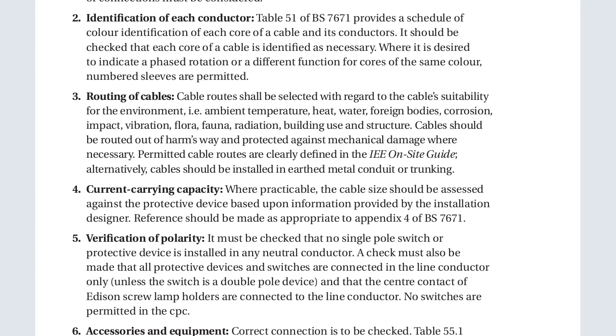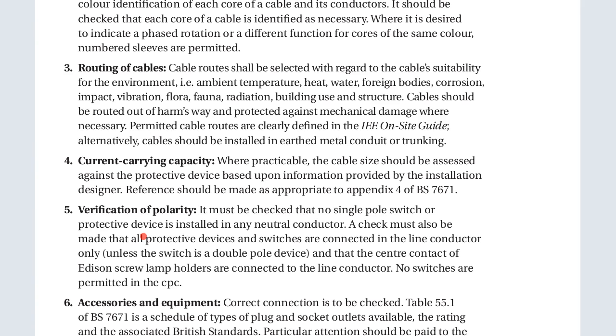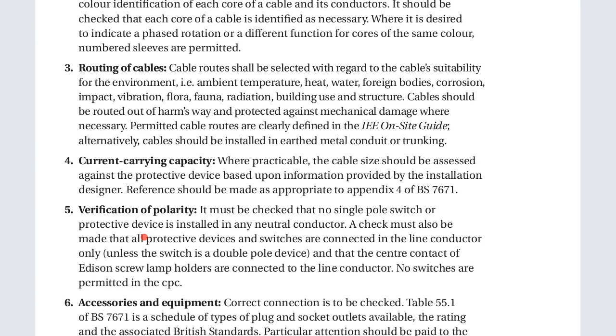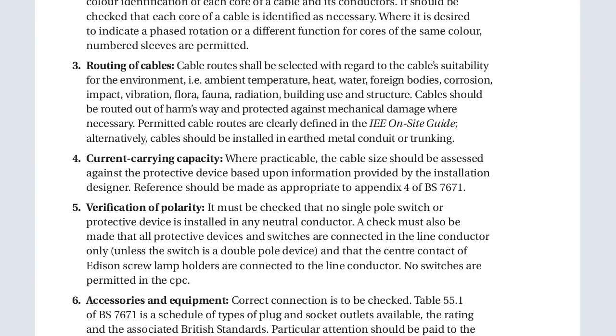Cable routes shall be selected with regard to the cable's suitability for the environment, i.e. the ambient temperature, heat, water, foreign bodies, corrosion, impact, vibration, flora, fauna, radiation, and building use and structure. That is, the cable should be routed out of harm's way and protected against mechanical damage where necessary. Permitted cable routes are clearly defined in the IEE On-Site Guide.